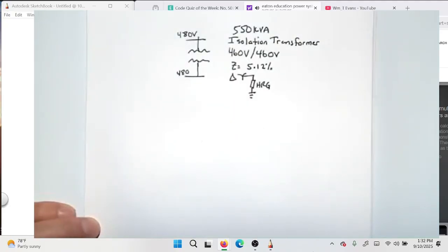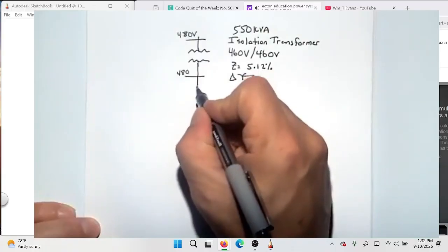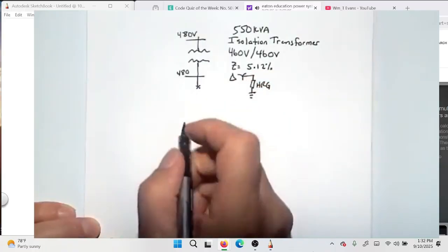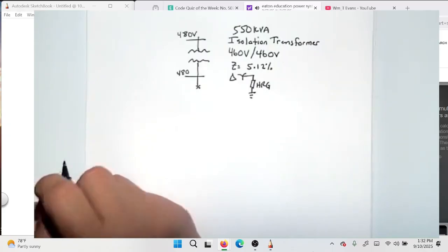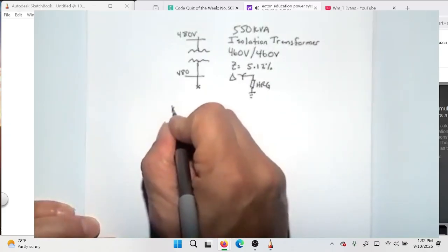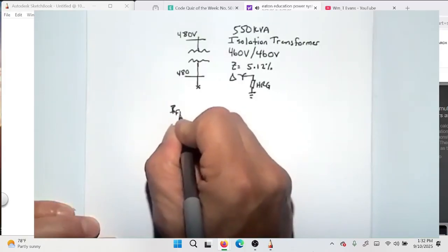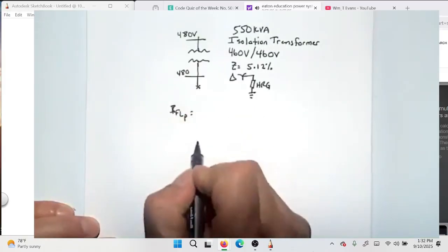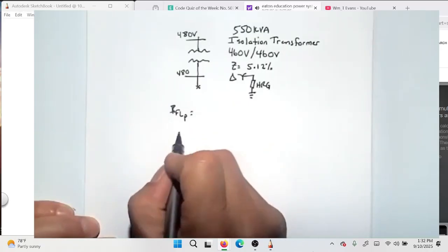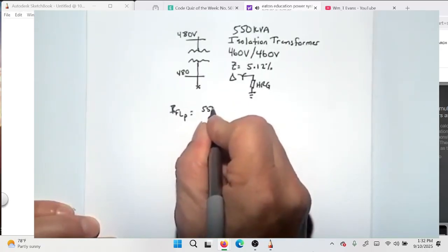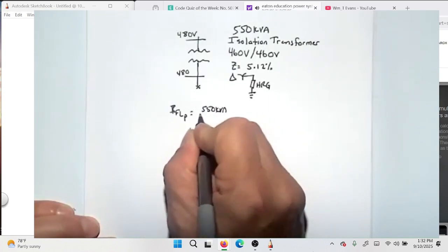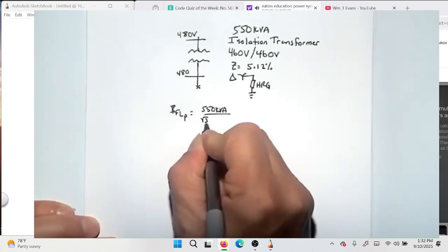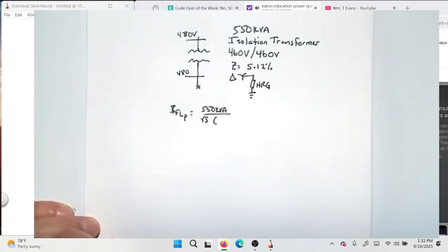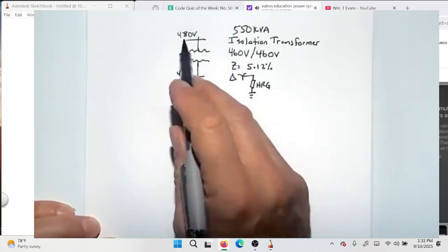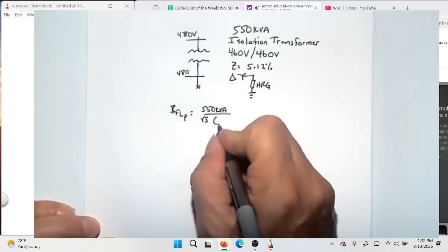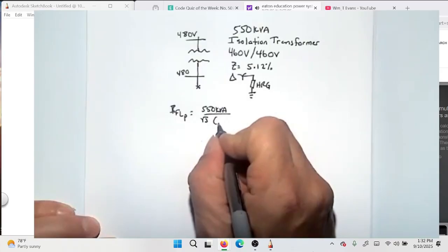But how are we going to calculate the full load amps on the primary and secondary and calculate our fault current? So again, we'll start with the same equation we've been using the whole time, I full load primary. And in this case, it's going to be the same as secondary, coincidentally, because the voltage is the same. It's going to be 550 kVA divided by square root of 3 kV line to line. Now, the tricky part is, do we use the rated value or do we use the actual applied voltage? What I'm going to tell you is let's do it both ways. Let's do 460.